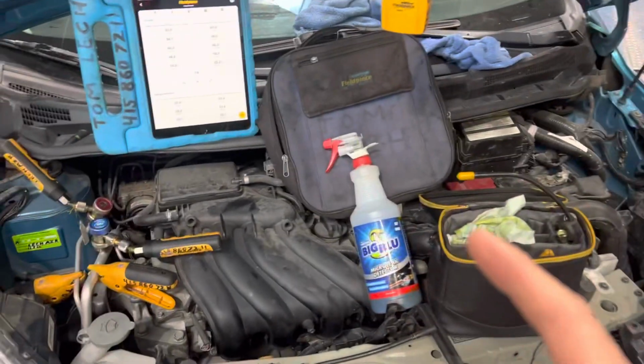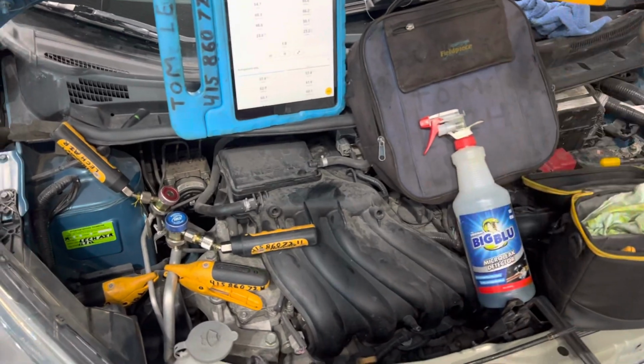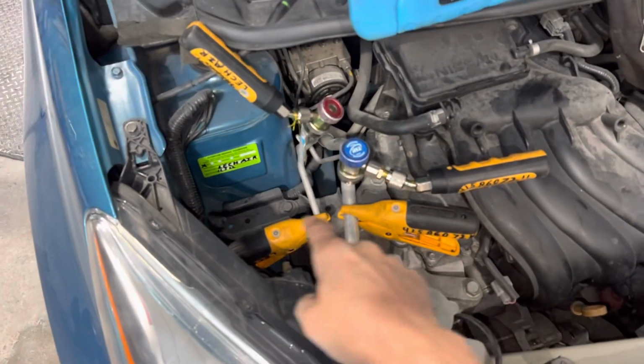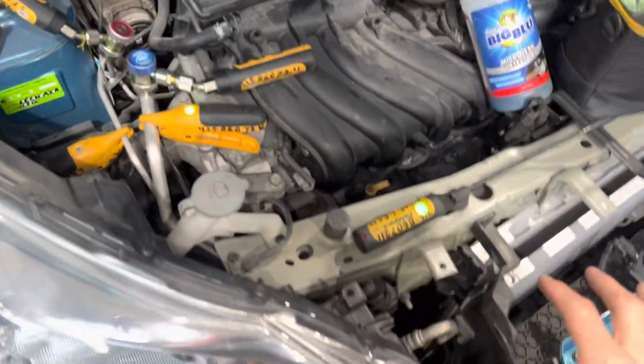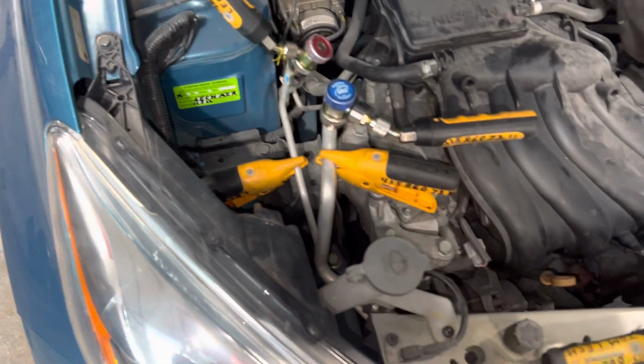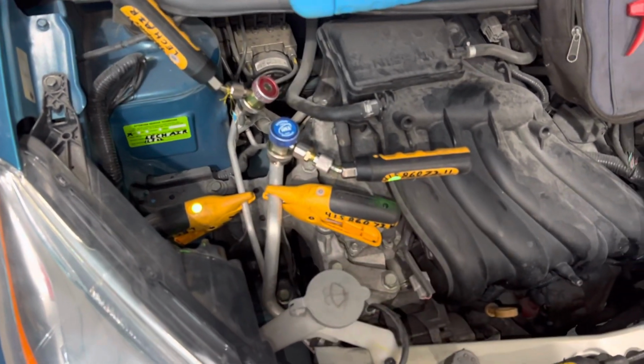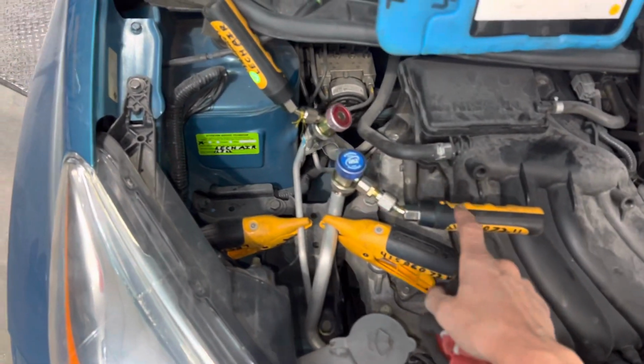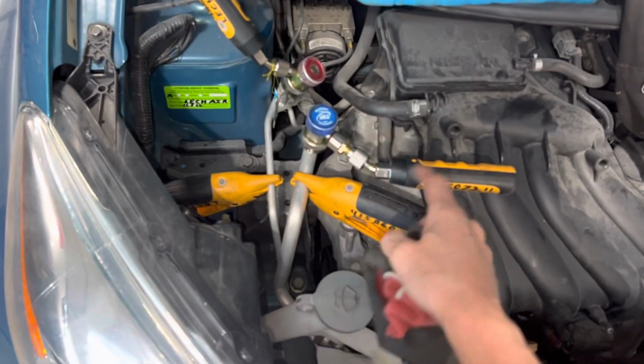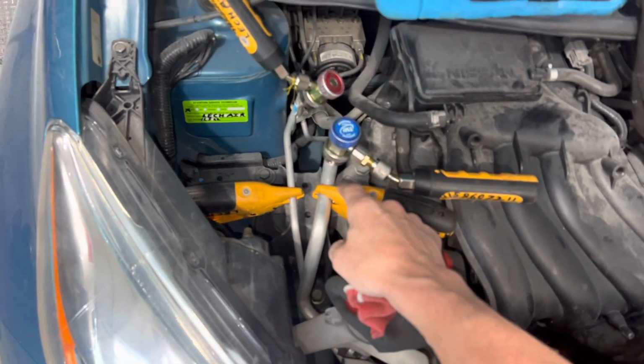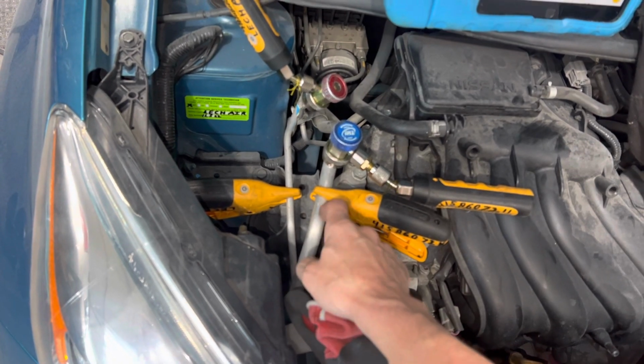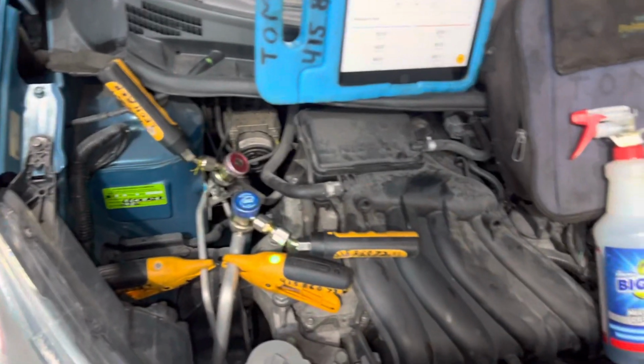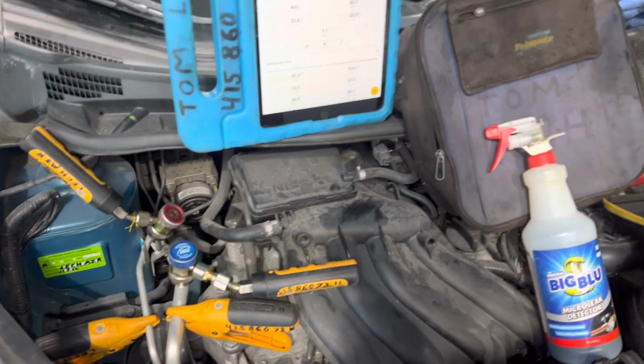Air conditioning on this Nissan Versa. I'm going to show you a different way since there are a lot of new subscribers who haven't seen me hook up gaugeless. I've already charged the system, and I've gone over how to do that without using gauges before, so I won't explain that here. I'm just showing using Bluetooth wireless pressure transducers for your pressures, and temperature sensors that sense the refrigerant temperature inside your vapor line and liquid line, so you can get your superheat and subcooling. So let's get on with it.